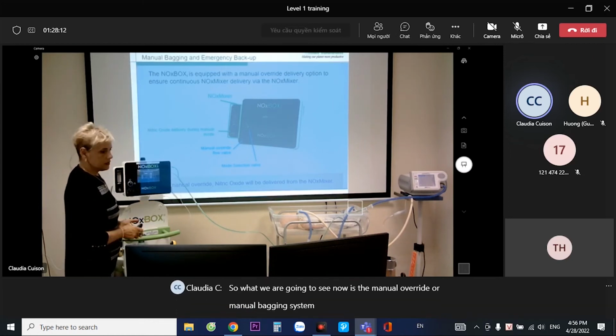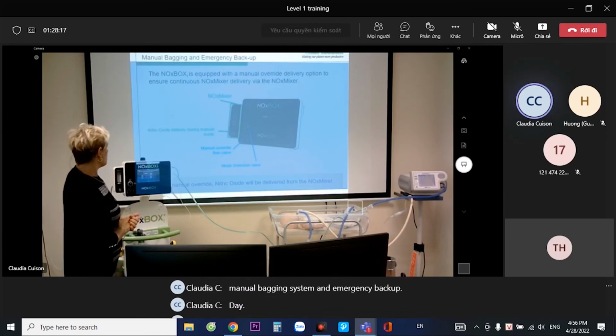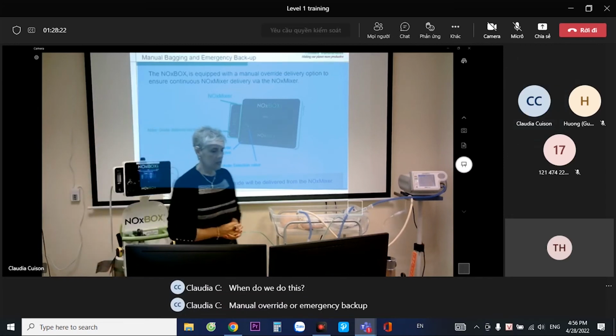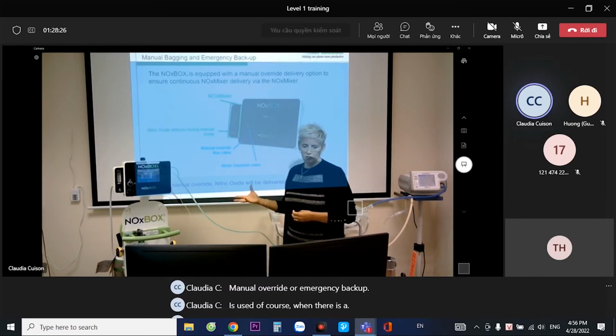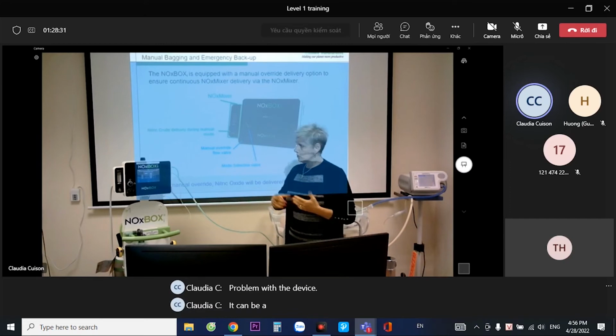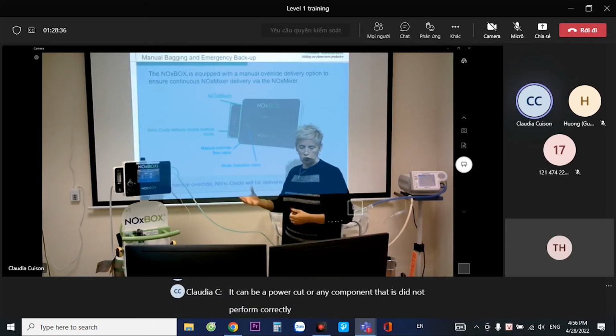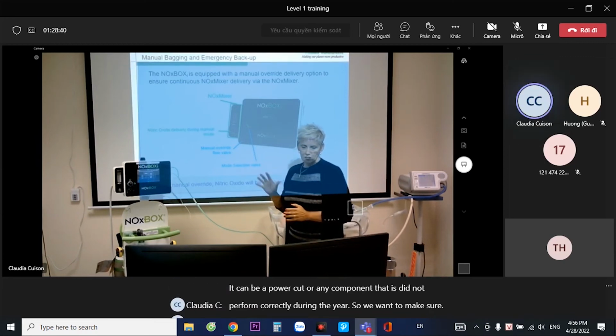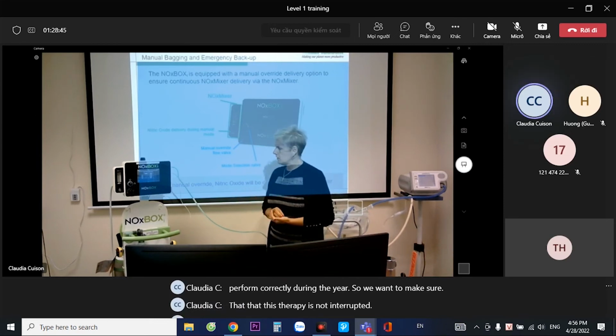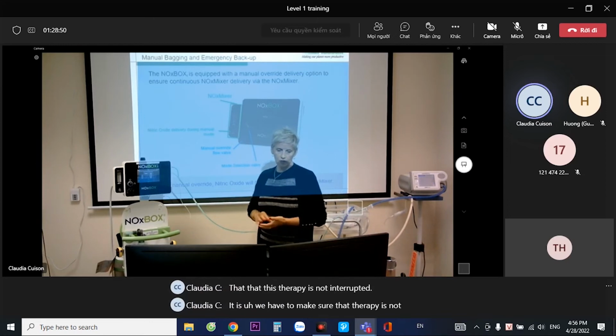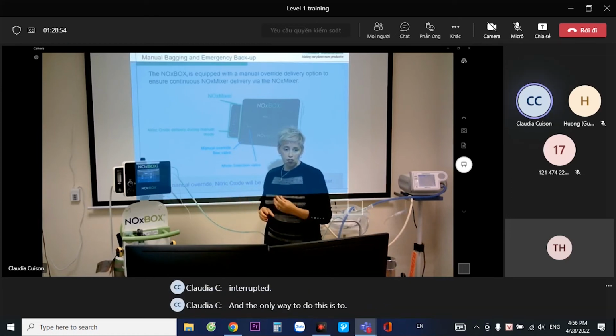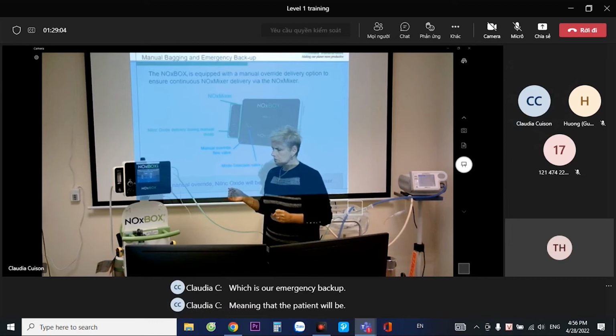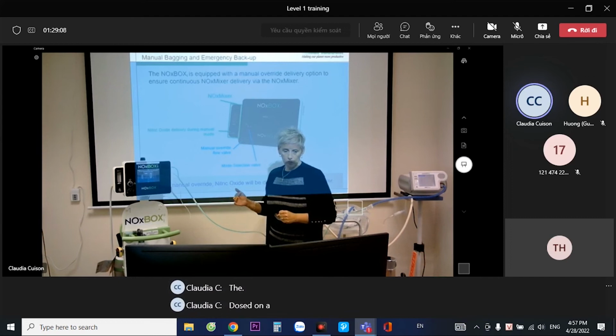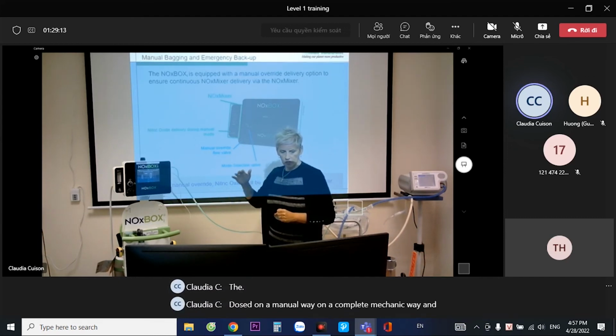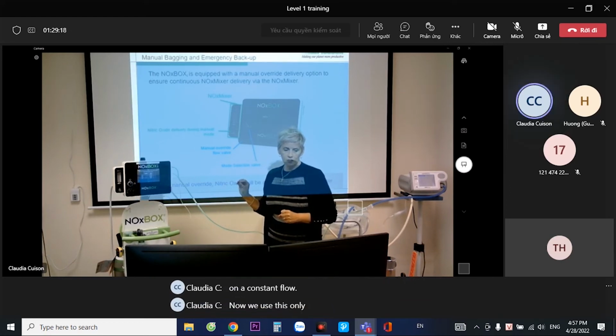So what we are going to see now is the manual override or manual bagging system and emergency backup. Okay. When do we do this? Manual override or emergency backup is used, of course, when there is a problem with the device. It can be a power cut or any component that did not perform correctly during the use. So we have to make sure that therapy is not interrupted. And the only way to do this is to provide a different system, which is our emergency backup, meaning that the patient will be dosed in a manual way, in a completely mechanical way, and on a constant flow.